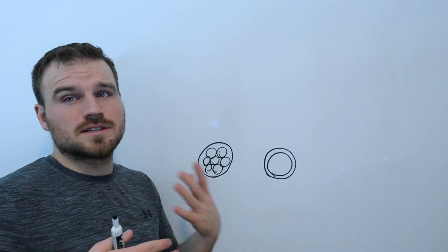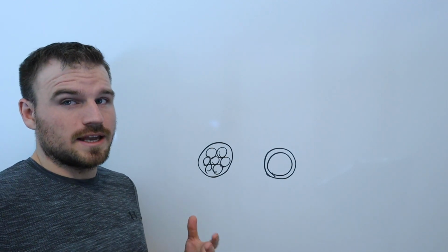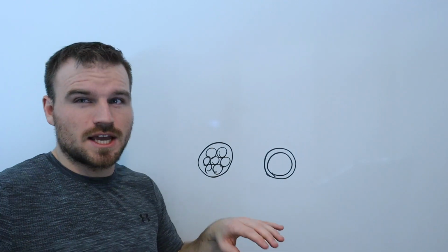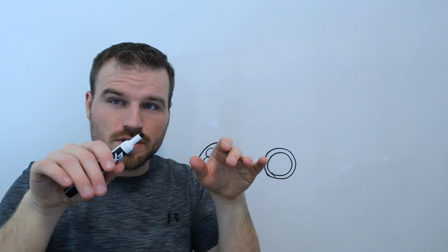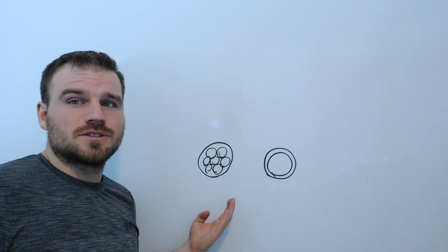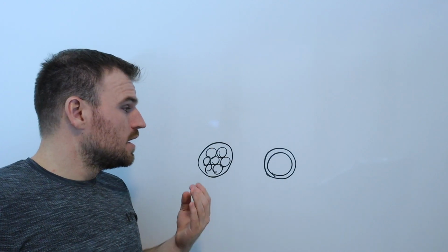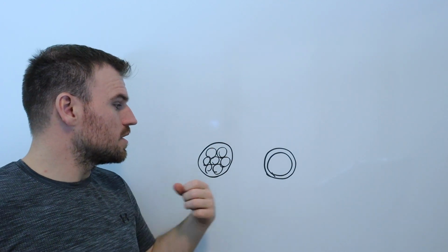Again, we're going to be playing with this a lot more, so you're going to notice that the solid core wire is a lot stiffer while the stranded wire is a lot more flexible, and it's not going to break as easy. So what happens if you take a wire and you're constantly working it back and forth? It's going to become work hardened, and then it'll potentially break. It's not to say that this can't happen with stranded wire, it's just a lot more difficult to do that with.